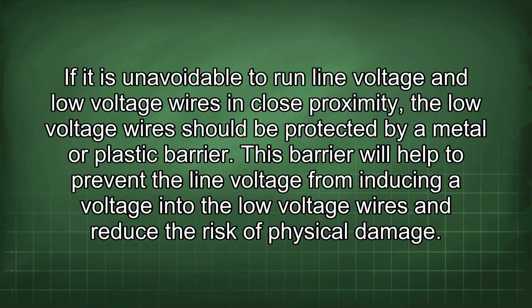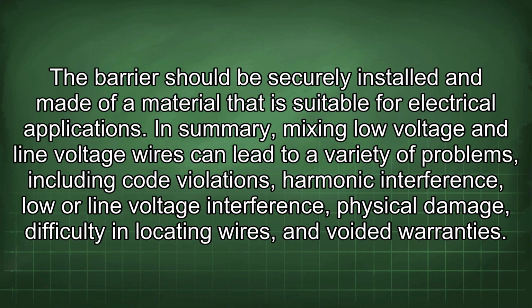If it is unavoidable to run line voltage and low voltage wires in close proximity, the low voltage wires should be protected by a metal or plastic barrier. This barrier will help to prevent the line voltage from inducing a voltage into the low voltage wires and reduce the risk of physical damage. The barrier should be securely installed and made of a material that is suitable for electrical applications.